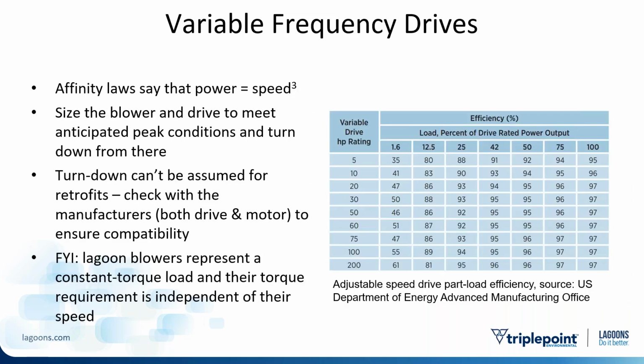Digging a little deeper on VFDs, the affinity laws tell us that power equals the cube of speed. And that's good to know, but that doesn't really tell the whole story. If you jump over to the chart on the right, you've got efficiency expressed as load, a percent of the drive's rated output, and then variable drive horsepower on the far left. And if you take a look, you'll see that there's a relatively nonlinear relationship here. You've got some changes and some sweet spots, and it's important to understand that sizing of VFDs and sizing of motors needs to be done very deliberately.